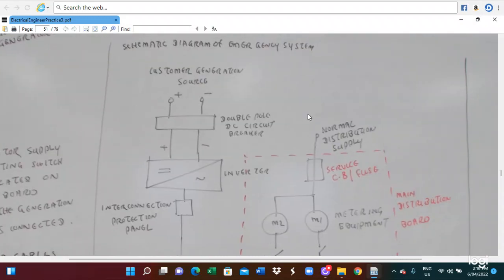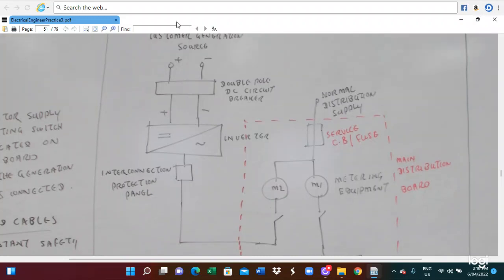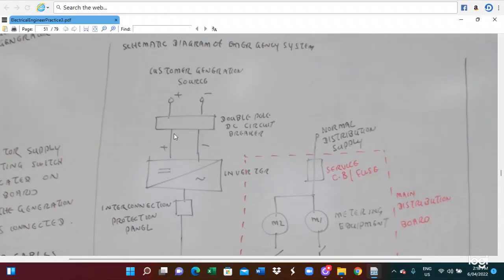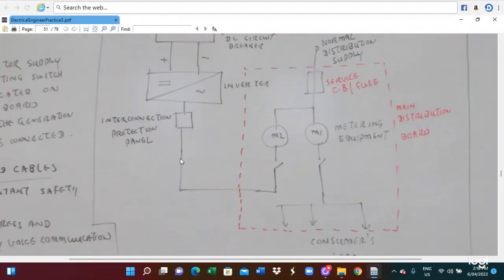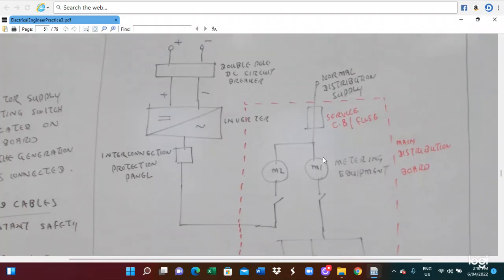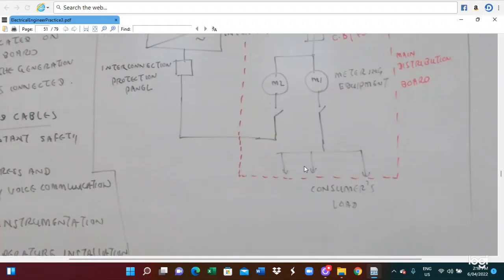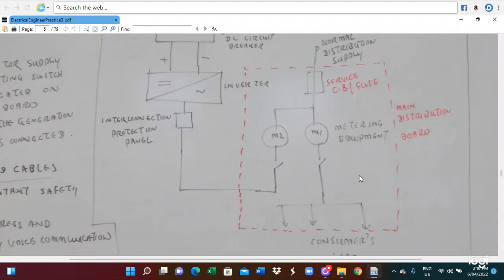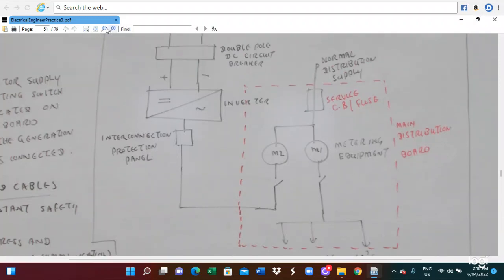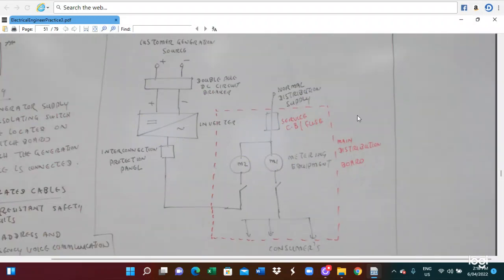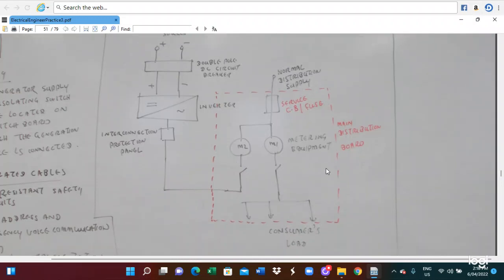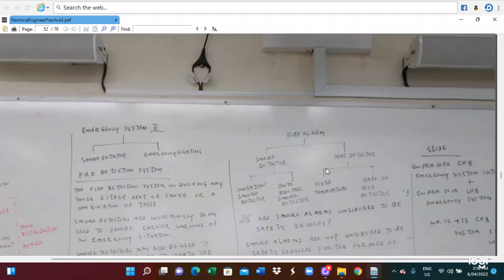In this case, here is a schematic diagram of the emergency system. So this is for customer generation. This is the inverter connected to the main switch, and also the normal distribution supply and the consumer load. So this is the connection of the customer generation source, and this is where the integration, interconnection, protection, inverter, and metering equipment are provided.